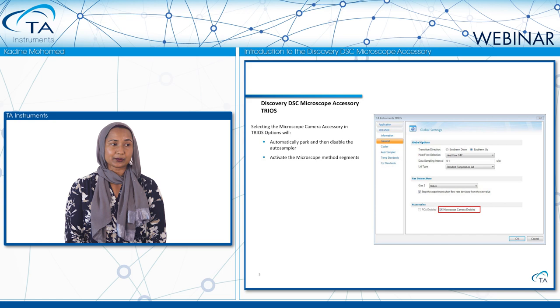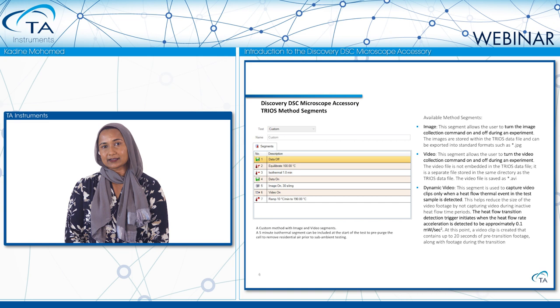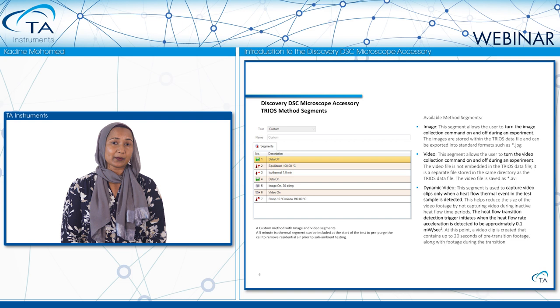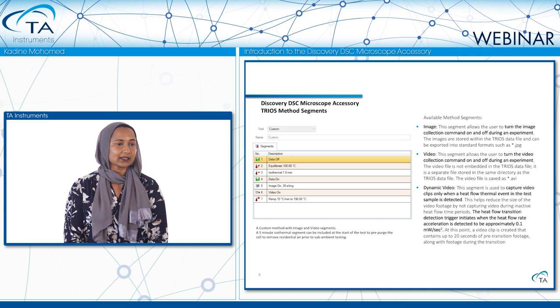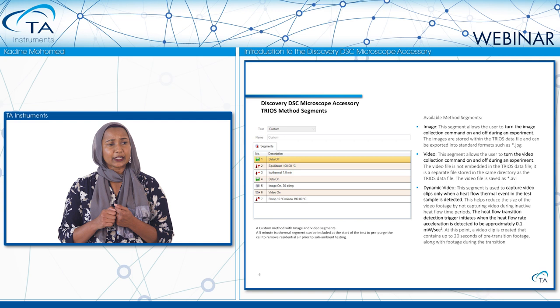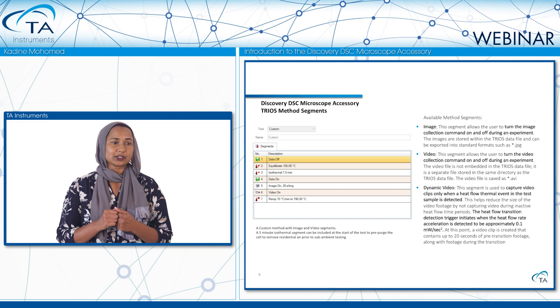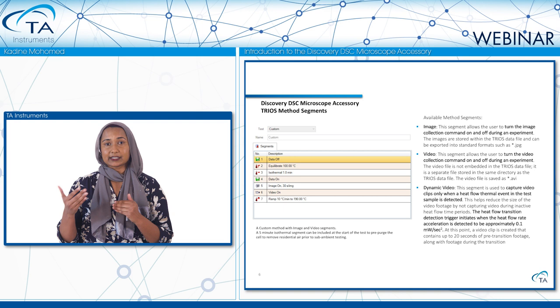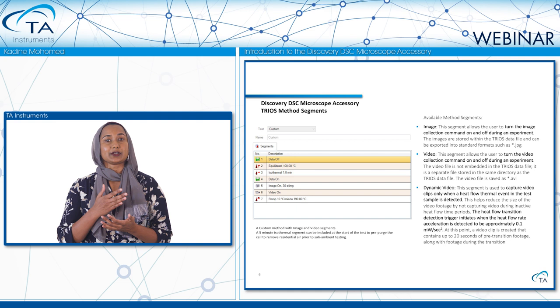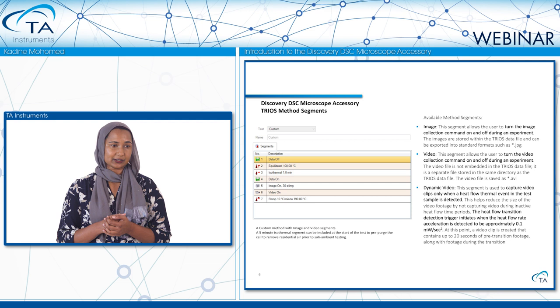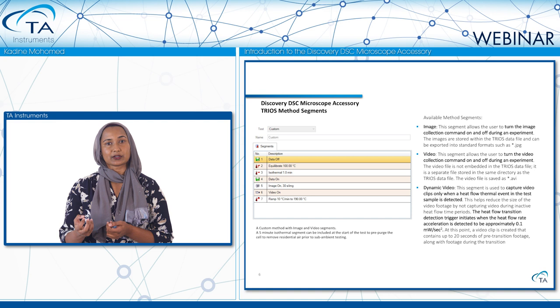There are three new method segments for the microscope camera, visible when you look at the test method in custom mode: image, video, and dynamic video. You can collect images and video within a single experiment. With the image segment, you can turn image collection on and off throughout the experiment — for instance, turning it on only when a transition is expected in a certain temperature range. These image files are stored within the TRIOS file and can be exported in standard formats such as JPEG.